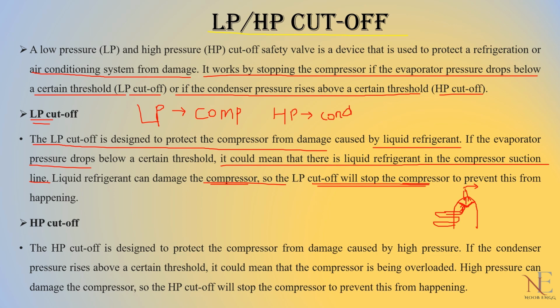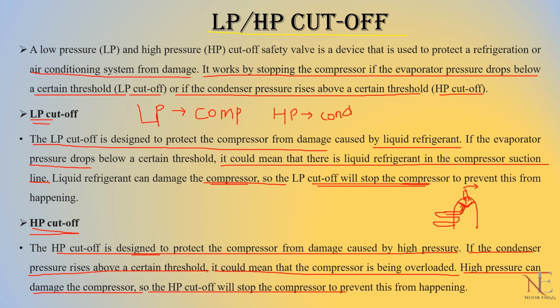And what is a high pressure cutoff? The HP is designed to protect the compressor from damage caused by high pressure. If the condenser pressure rises above a certain threshold point, it could mean that the compressor is being overloaded. High pressure can damage the compressors. So the HP will cut off and stop the compressor to prevent this from happening.